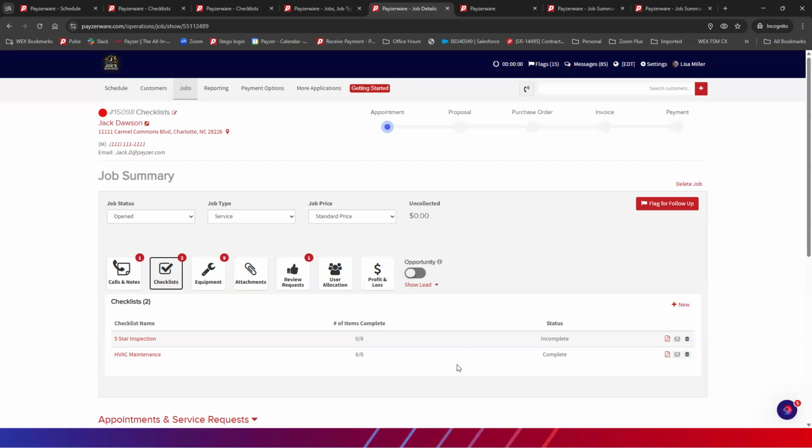And the first thing they're going to say is, well, it was probably the install. And at that point, you can print this out, you can email it to them and show them on your install that you did a good install, the pressures were in line with where they were supposed to be, everything was checked, and now you have a leg to stand on.